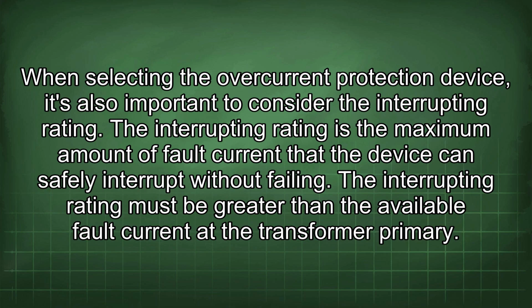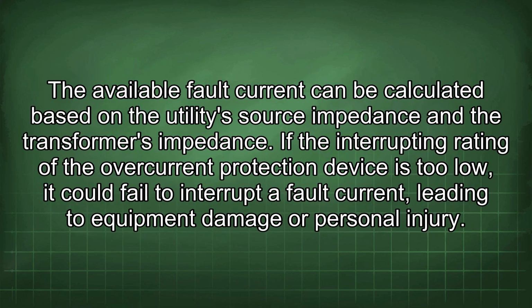When selecting the overcurrent protection device, it's also important to consider the interrupting rating. The interrupting rating is the maximum amount of fault current that the device can safely interrupt without failing. The interrupting rating must be greater than the available fault current at the transformer primary. The available fault current can be calculated based on the utility source impedance and the transformer's impedance. If the interrupting rating of the overcurrent protection device is too low, it could fail to interrupt a fault current, leading to equipment damage or personal injury.